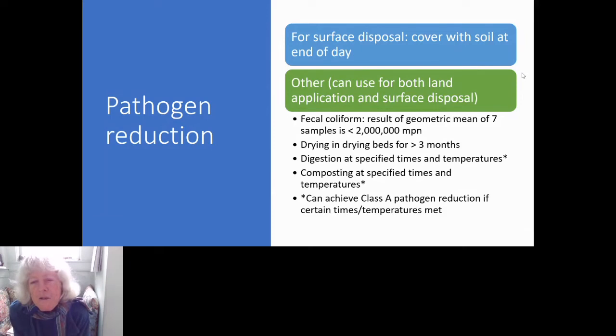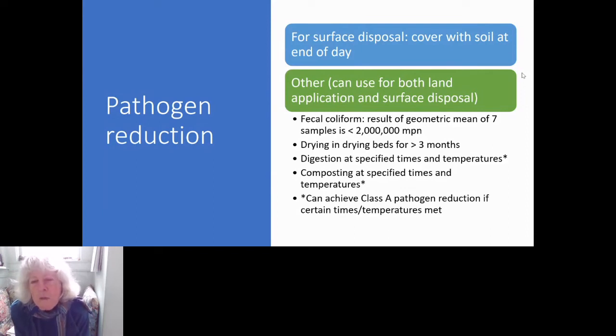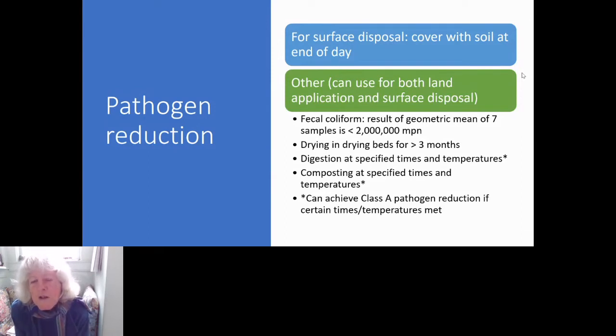There are two classes of pathogen reduction: Class B is suitable for land application on non-food crops, and Class A is considered pathogen-free so you can distribute it to the general public. If you digest or compost at high temperatures you can achieve Class A — this is spelled out in the rule as to what times and temperatures you need to meet. The Hoopa Tribe was looking at composting at high temperatures for future septage and wastewater solids, so the resulting compost could be used without further restrictions.